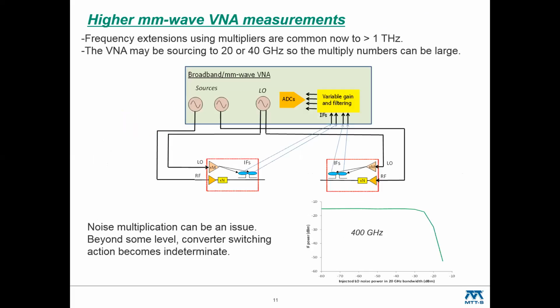So how do these get implemented in practice? One may already be using these kind of structures where you have millimeter wave modules attached to some microwave VNA. This is a common approach for practical logistical reasons, but it also valuably gets the test port out very close to the DUT, or to the wafer probe, or the final structure. So you don't have a crazy amount of loss between the instrument port and the device, which impacts dynamic range, stability, and other things.